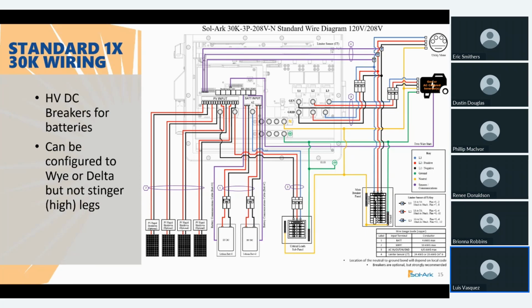But maybe you want to keep some loads in the main panel because you don't want to use your battery to cover those in an off-grid situation. Even if you separate those loads, you still have the option to send PV power to both panels, as long as you have CT sensors installed.